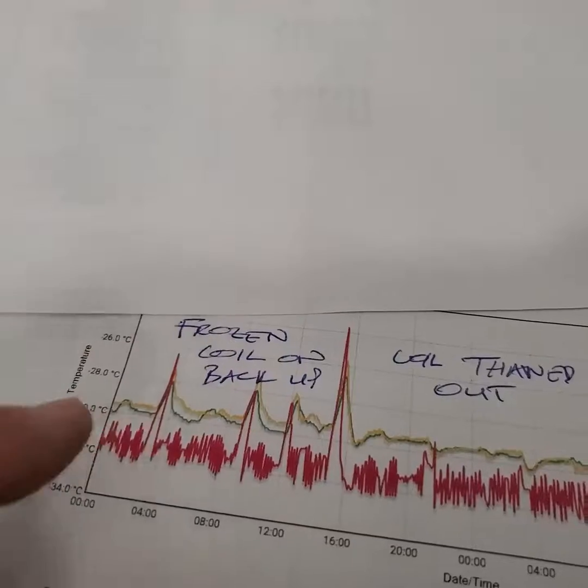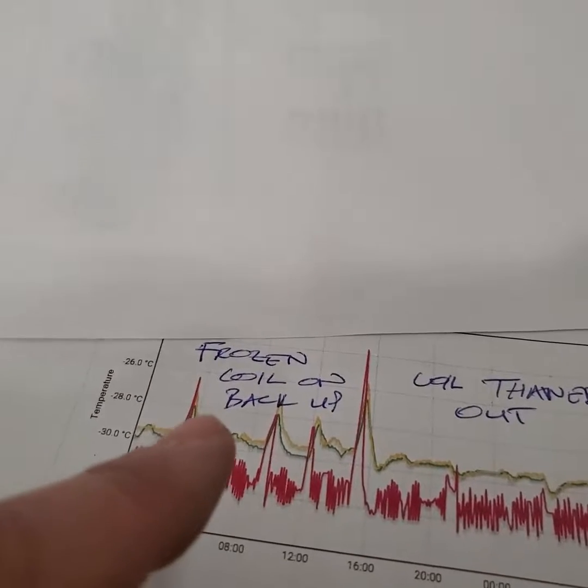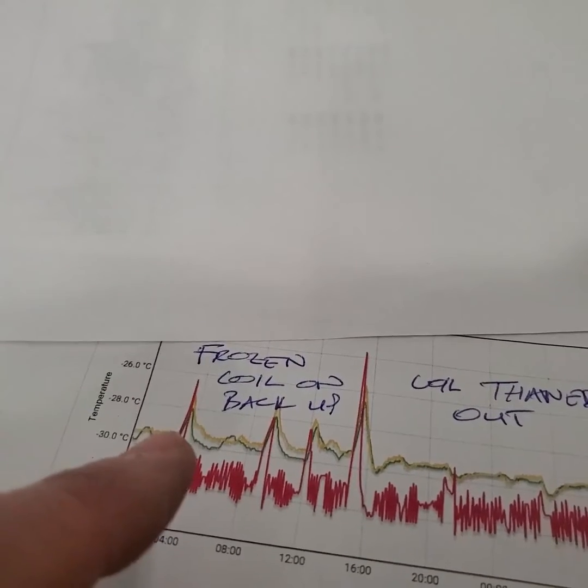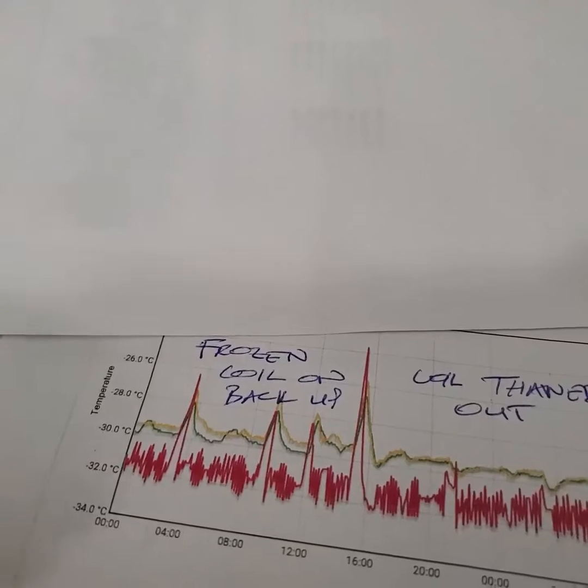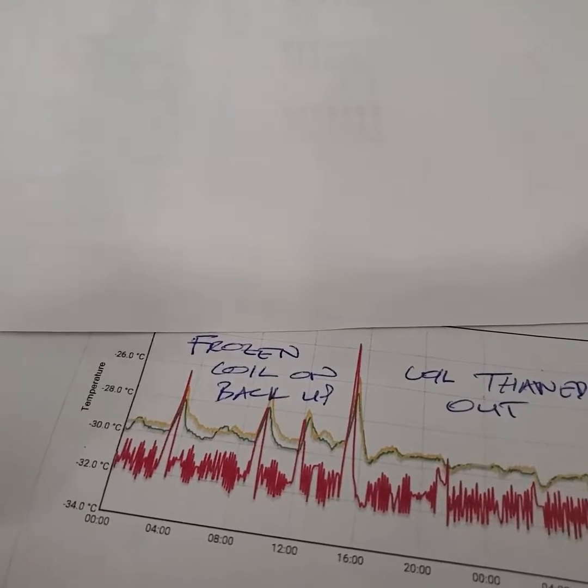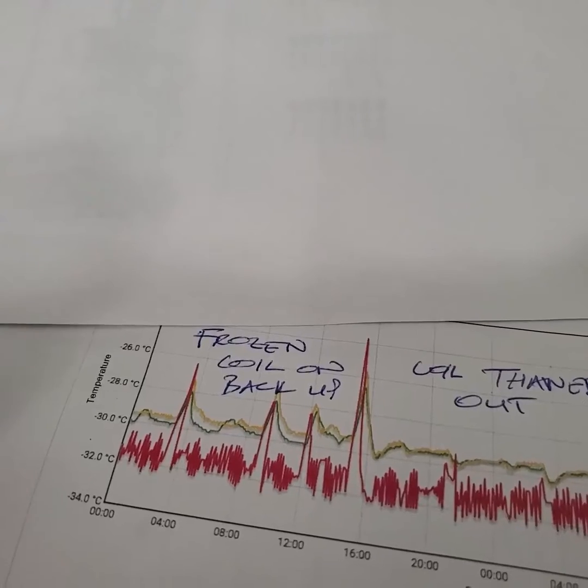This is the whole entire box. What happens is when the primary unit goes into defrost, the backup is supposed to hold the temperature of the box. Now it couldn't because the coil was frozen up and we couldn't defrost that coil.